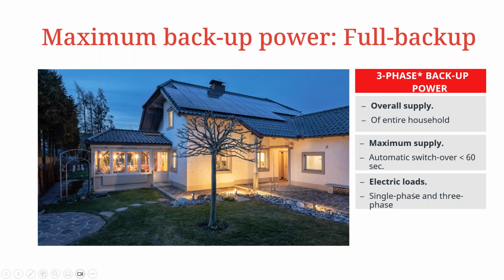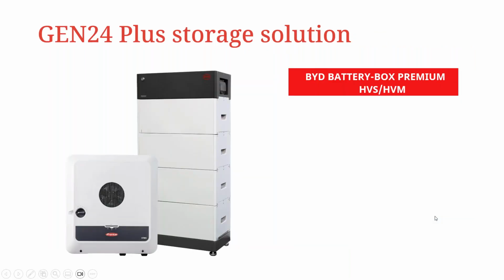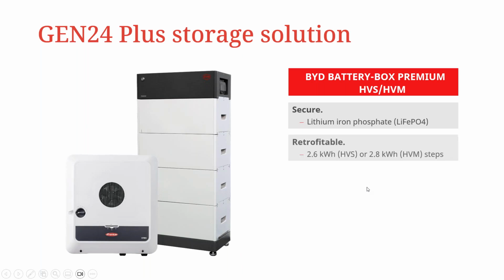And then also you can cover full electrical load. So it can be single phase and 3-phase backup. And then maximum energy consumption. So again, mentioning the parallel discharging or multi-flow design. With the BYD batteries, they are lithium iron phosphate batteries. So they are retrofittable. So you can have a single power stack, which is 2.6 kilowatt hours, so the HVS, or the 2.8 kilowatt hour HVM steps.